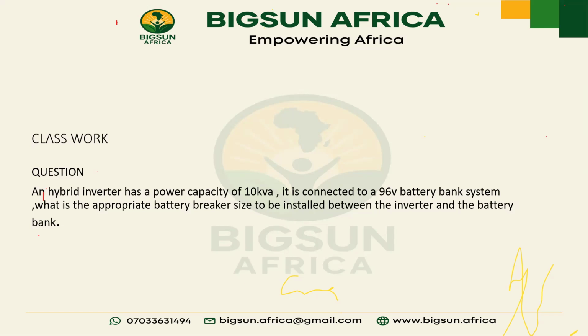But whenever you need to convert your inverter kVA to kilowatts, you know what to do. You multiply it by 0.8. Then when you need to convert from kilowatts to kVA, you divide by 0.8. Are we clear with that? How to convert kVA to kilowatts, please?